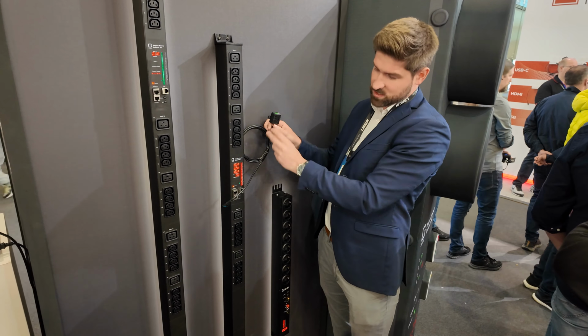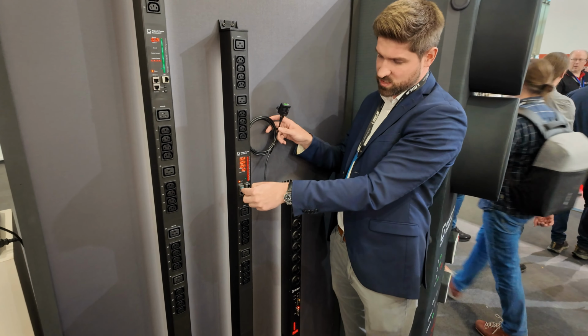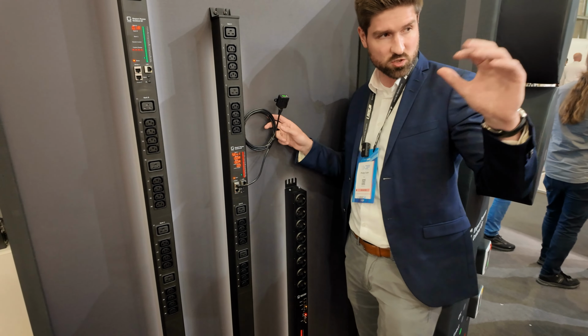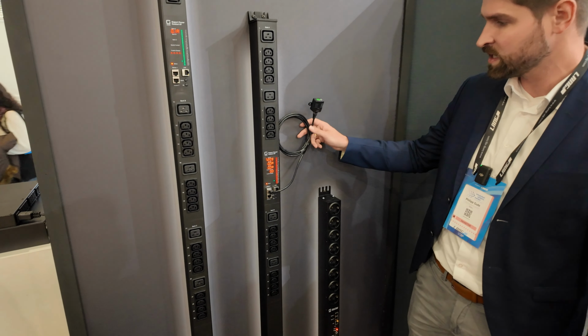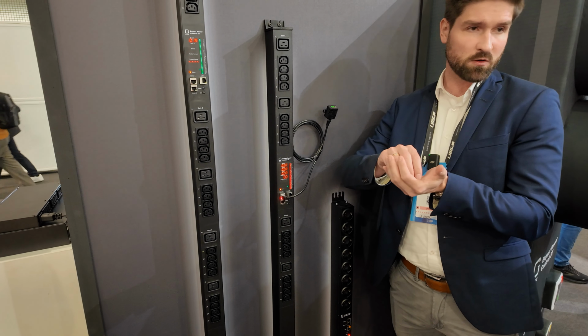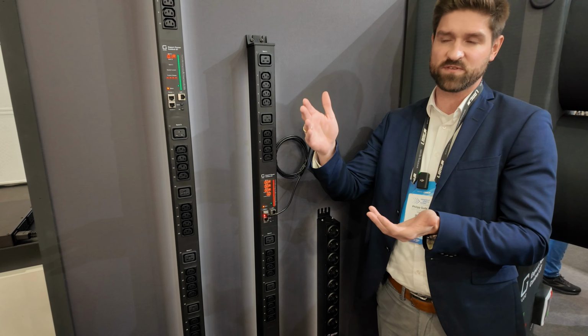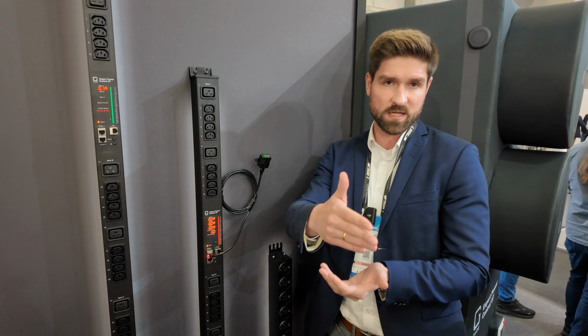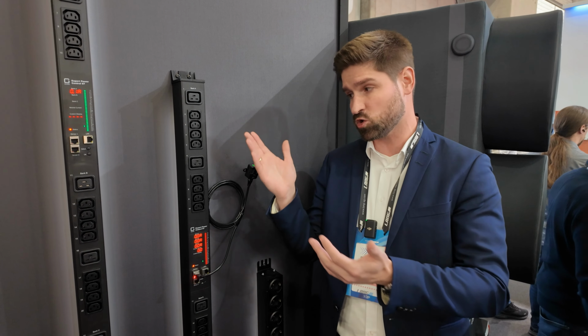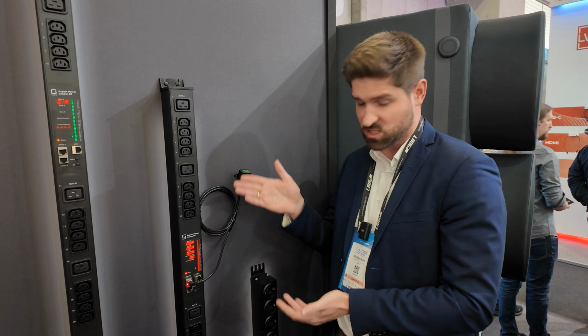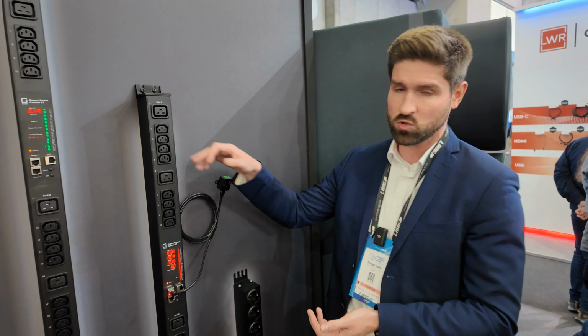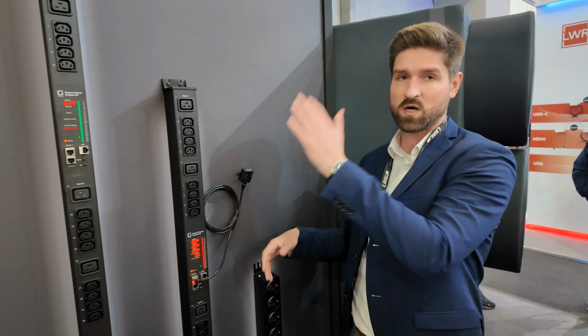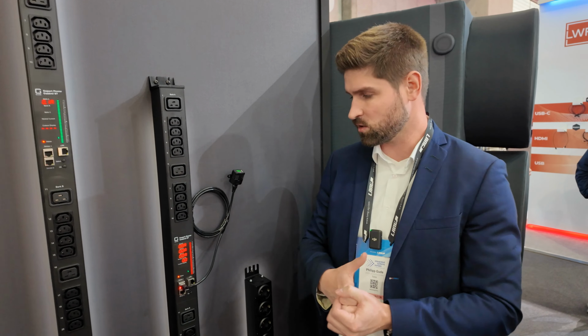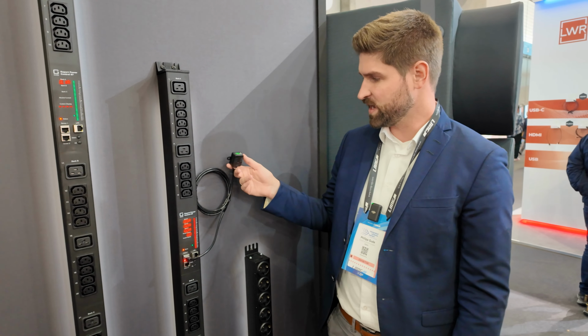You can also get all this data into Crestron, so the temperature you can pull into Crestron and see how hot it is. You can put thresholds in our PDU, and if it's getting too hot, you get an email notification saying it's too hot. You could also switch outlets or do fan control, so for example on port 2 you have a fan, and if temperature is too high, you turn on the fan. That's also possible.